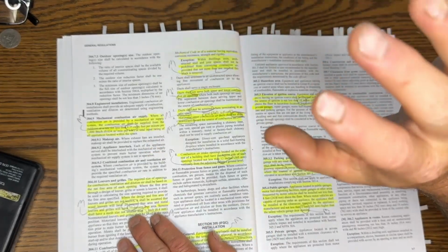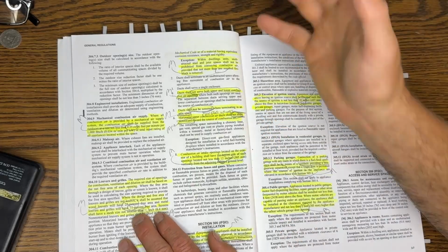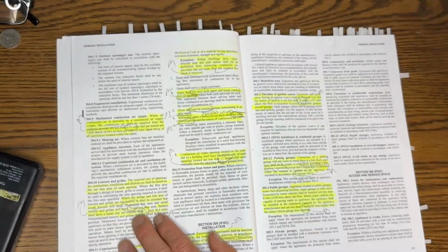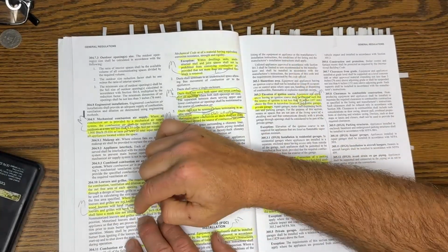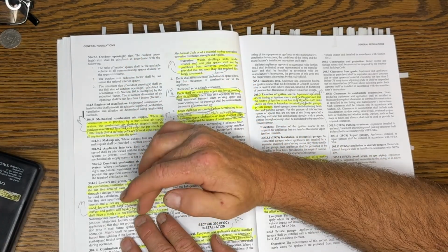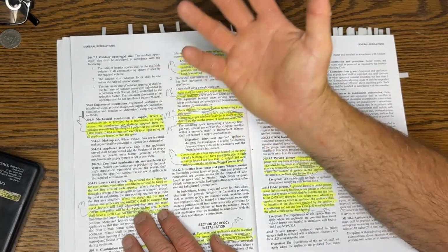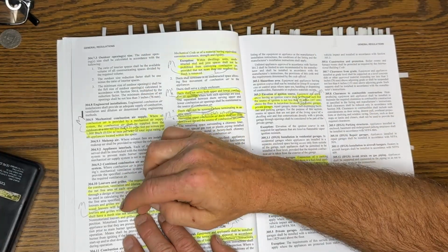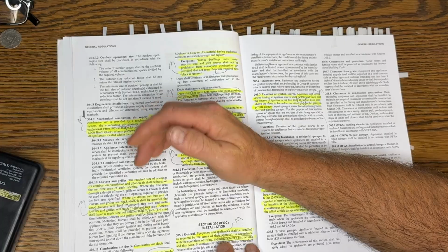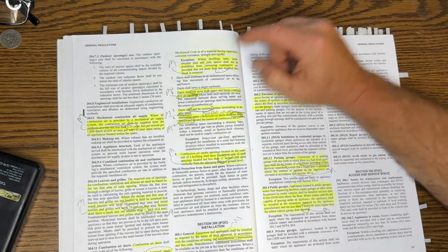They'll ask you, you'll have the area spec'd, and then they'll say there's a wood louver on it. So what does the overall area need to be? Just keep in mind, let's say you had to have 100 square inches, but you have a 75% derating. That means you end up needing 400 square inches type thing. So that's what ends up happening there, if that makes sense. Okay, combustion air ducts, galvanized steel.